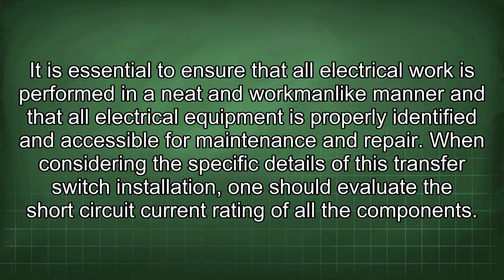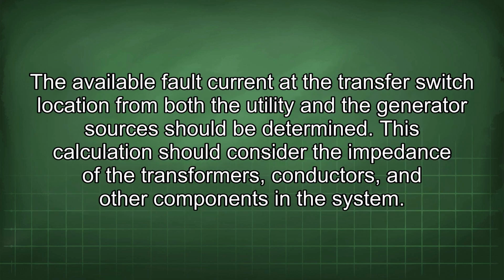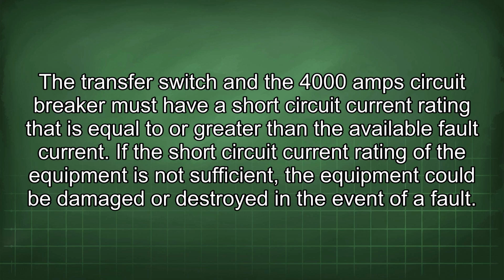When considering the specific details of this transfer switch installation, one should evaluate the short circuit current rating of all the components. The available fault current at the transfer switch location from both the utility and the generator sources should be determined. This calculation should consider the impedance of the transformers, conductors, and other components in the system. The transfer switch and the 4000 amp circuit breaker must have a short circuit current rating that is equal to or greater than the available fault current. If the short circuit current rating of the equipment is not sufficient, the equipment could be damaged or destroyed in the event of a fault.